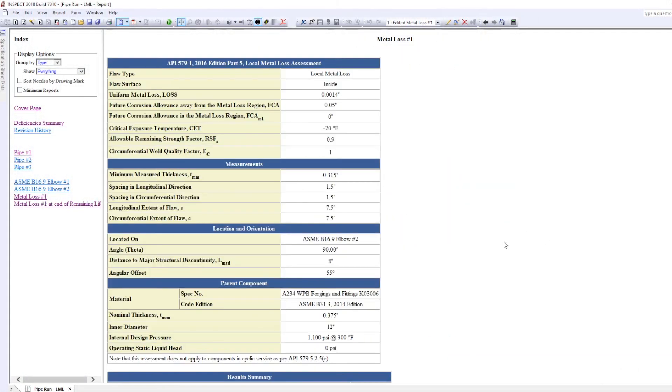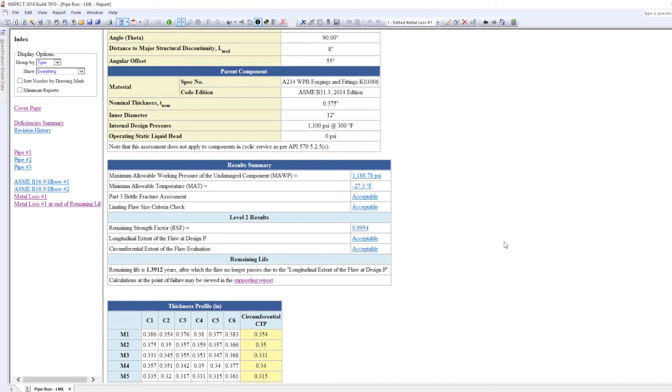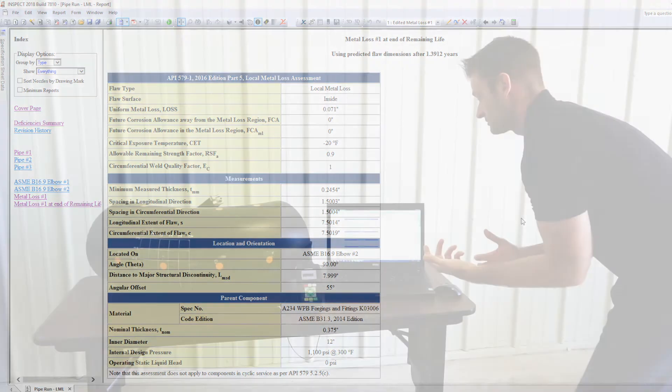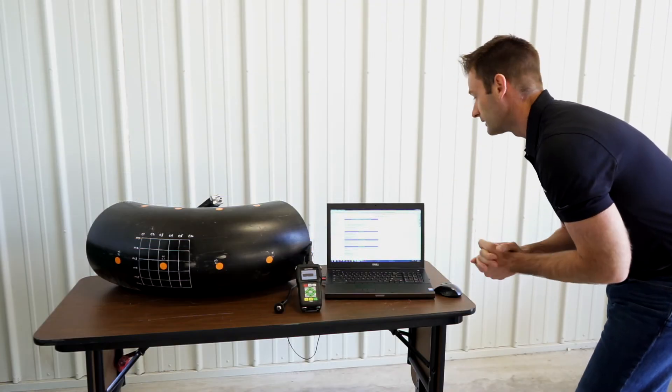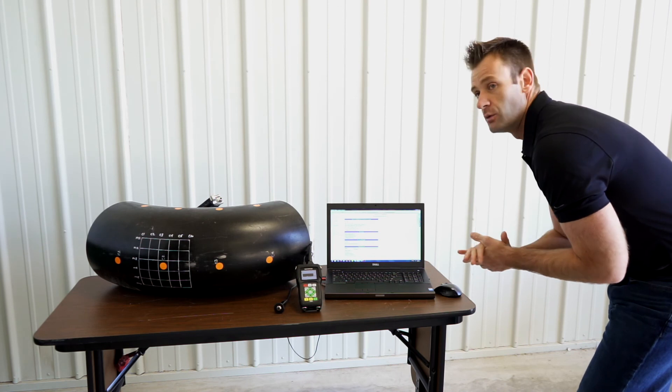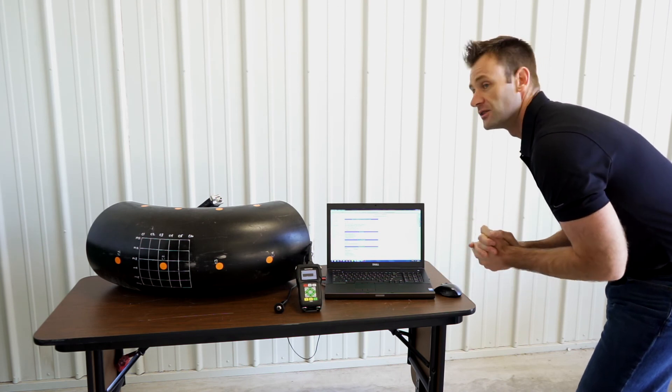So very quickly when I'm in the field I can click on the metal loss, come down here. As you can see from the results everything is acceptable. So it passes our fitness for service assessment. And again we've run levels 1 and 2. And we can also check out the remaining life that I had set up earlier. So as you can see using the predicted flaw dimensions we have 1.3 years remaining. So if your next scheduled shutdown is within the year we're fine. We can continue to run this. But we now know when we have to go back and either replace or repair it.